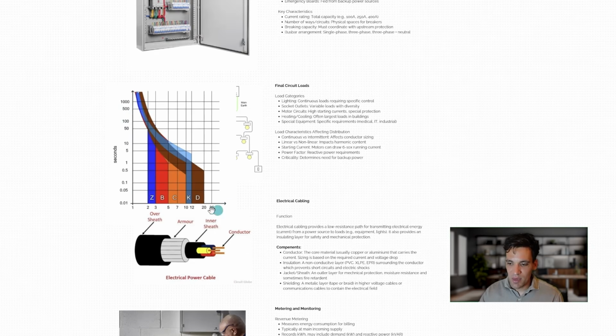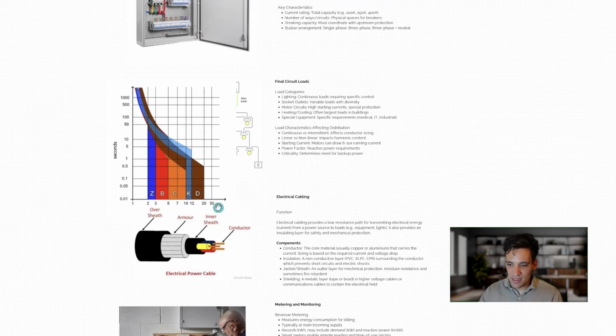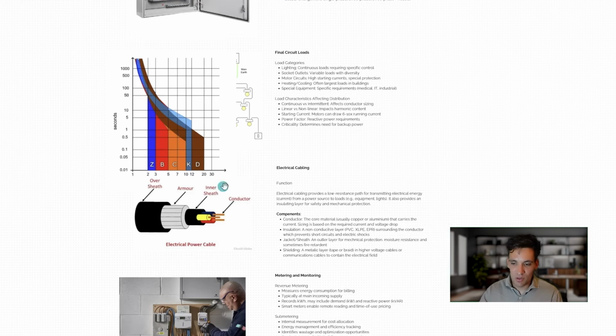So what this means is you have the normal operating current, a multiple of that. So you can see with a normal operating current of 1, the circuit will never trip. It just operates as normal. But if you have an overcurrent of 2, you can choose different circuit breaker ratings that will determine how quickly it trips. So if you get a Z-class circuit breaker and you get a double overcurrent, so twice what the normal operating current is, it'll trip in 10 seconds. If you get a 20 times rating, a D-class circuit breaker will trip in 0.5 second.